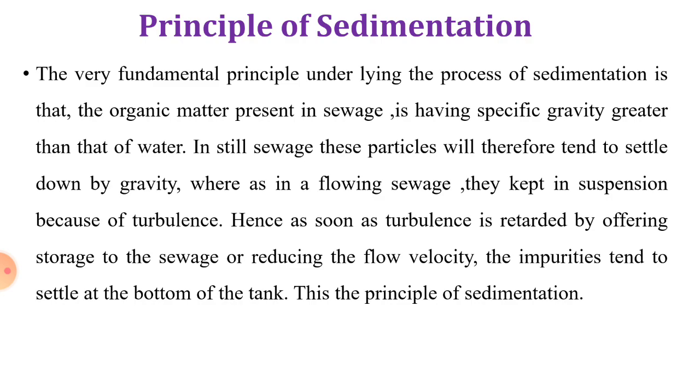Principle behind the sedimentation. The very fundamental principle underlying the process of sedimentation is that the organic matter present in the sewage has a specific gravity greater than the water. In still sewage, these particles will therefore tend to settle down by gravity, whereas in flowing sewage they are kept in suspension because of the turbulence.